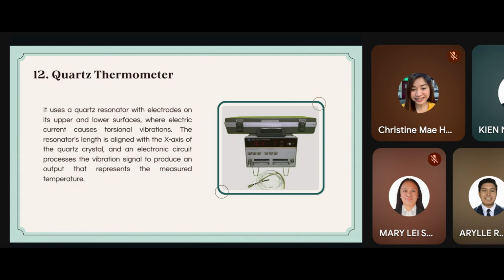Next is quartz thermometer. It uses a quartz resonator with electrodes on its upper and lower surfaces, where electric current causes torsional vibrations. The resonator's length is aligned with the x-axis of the quartz crystal, and an electronic circuit processes the vibration signal to produce an output that represents the measured temperature. Ang quartz thermometer ay gumagamit ng quartz resonator na pinagdadaluyan ng kuryente para mag-vibrate. Yung signal na galing sa vibration ay kino-convert ng circuit para malaman ang temperature.